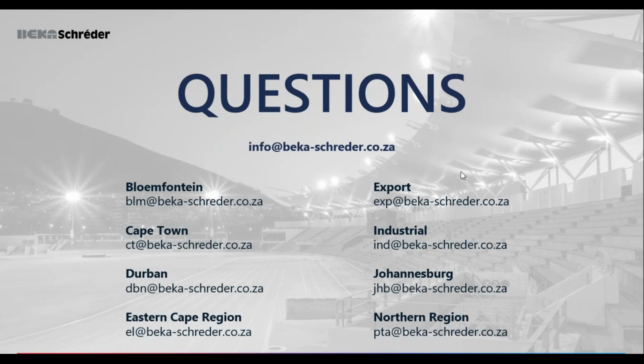Okay, so then on the lighting control, Dani, we've got a question. On the lighting control again, how far should the local server be positioned to get the mentioned Bluetooth connection, especially in sports and recreation applications, which are normally far from the buildings where servers are generally located? Yes, Mr. Boswa, to answer you as well as possible, obviously, like I said, Bluetooth connectivity has limitations, as everybody knows, and for outdoor use, even more so. The components we used have a maximum distance of about 50 meters range connectivity.